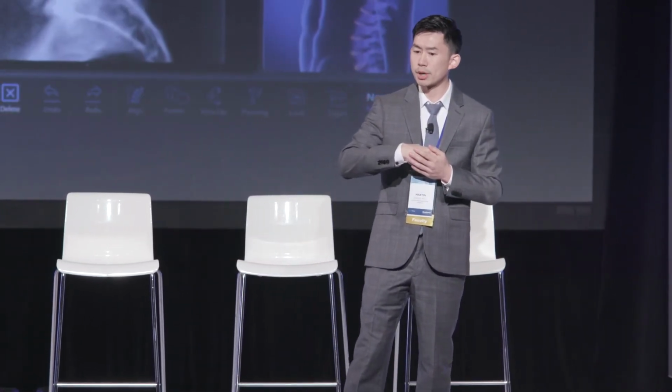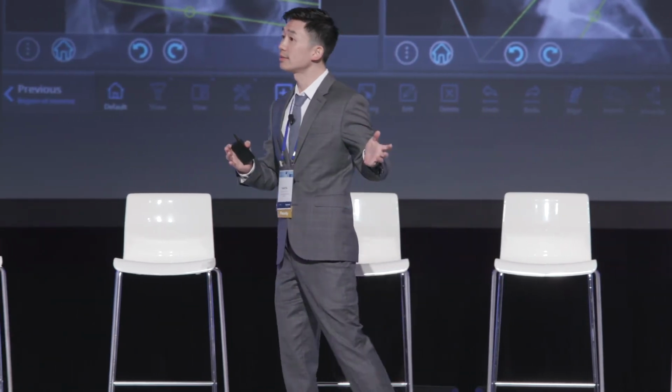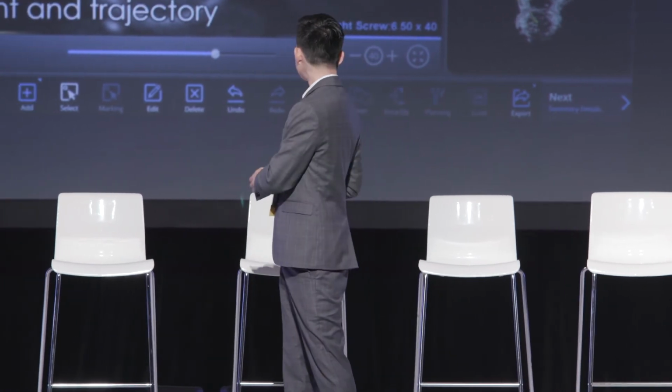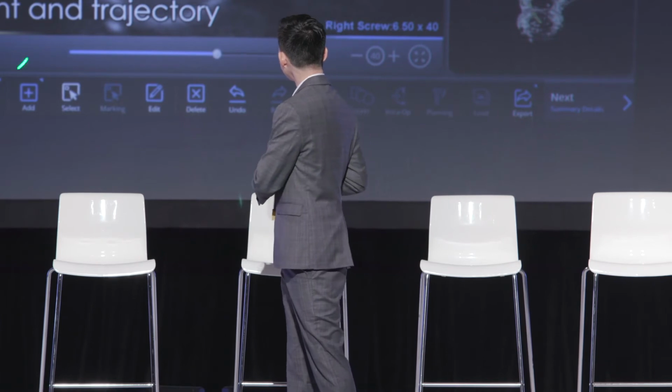So again, you log in, you pick out your patient, you mark out where you want the robot to focus on with regards to the levels of the spine. The software then auto-segments this, and you can check it to make sure that it is what you want it to do. You pick your level, and then it labels everything else in the spine. And once that's done, you go to this planning screen where at the L4 level, you can see I am literally deciding my implant. You can take a look at the bottom of the screen here, right?